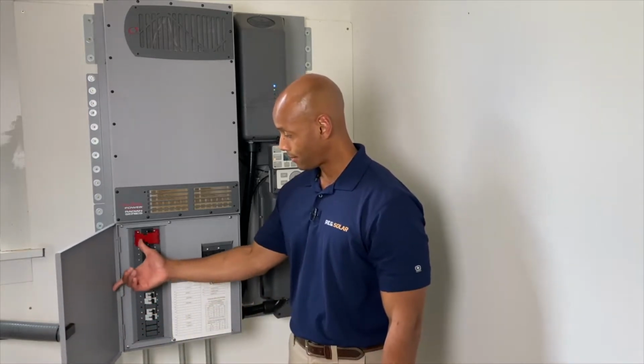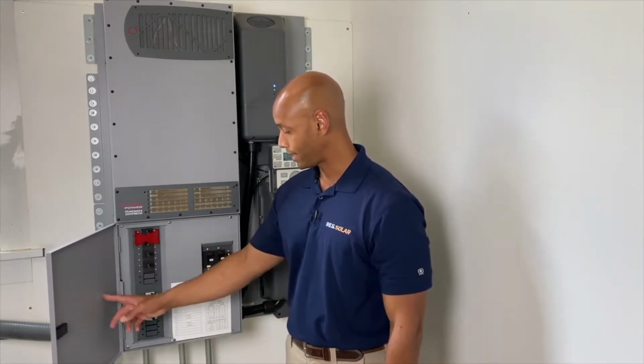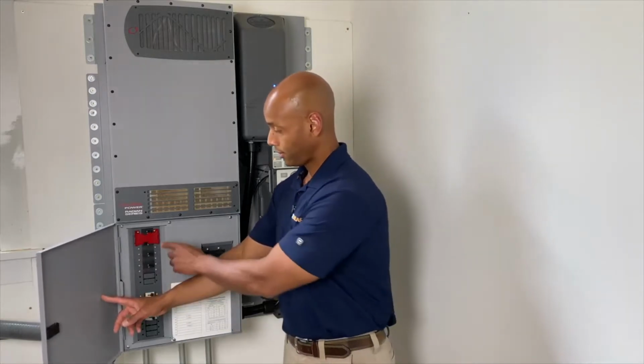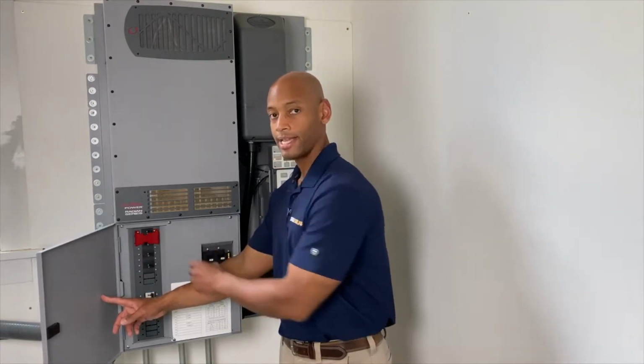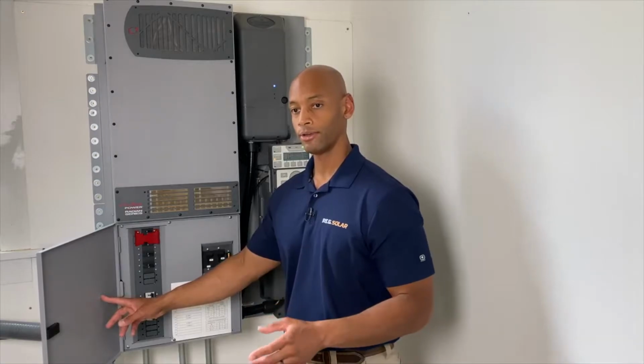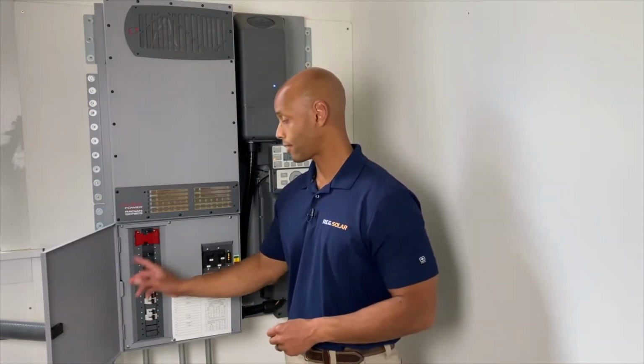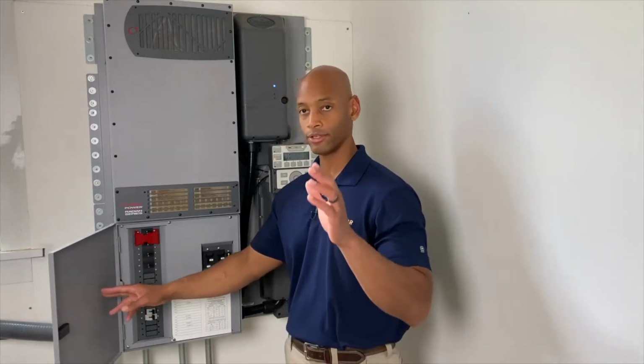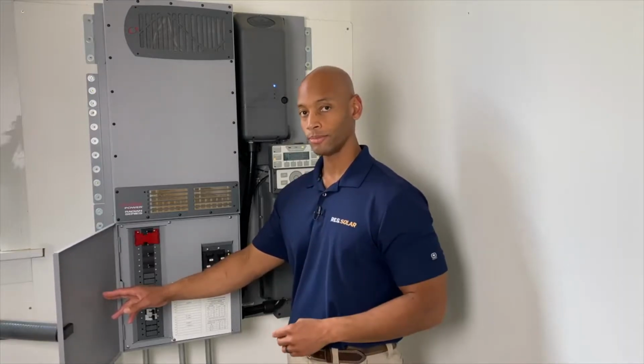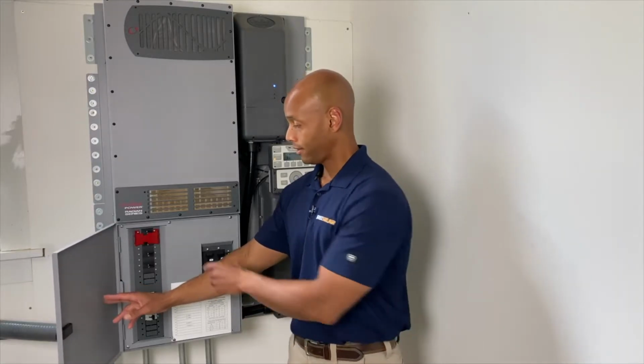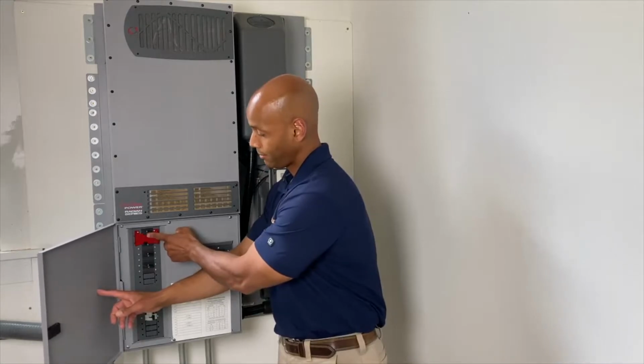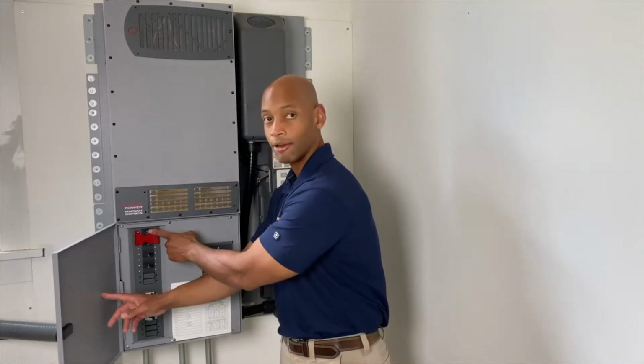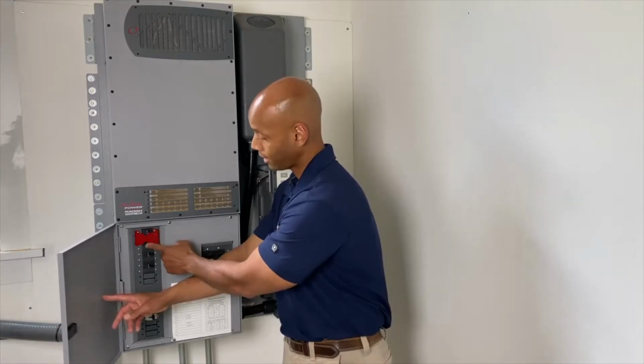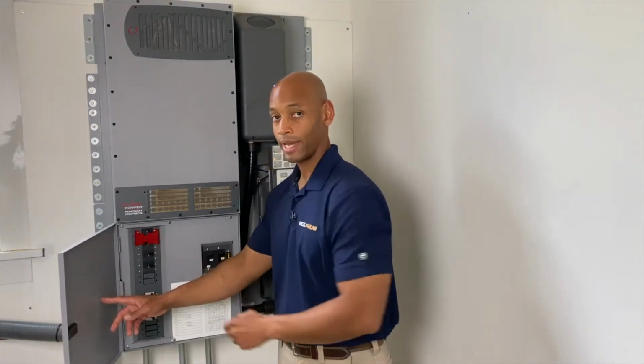And then up here, I'm going to start at the top and work my way down. The top circuit breaker here is AC output to your critical loads in the house. If I were to cut power here, all of my emergency loads panel would lose power. Now, this red clip here is called an interlock, and the AC output from the inverter is interlocked with the grid bypass switch.